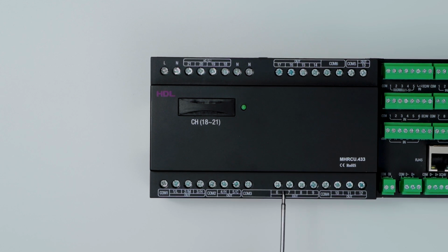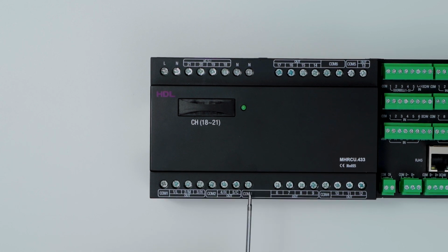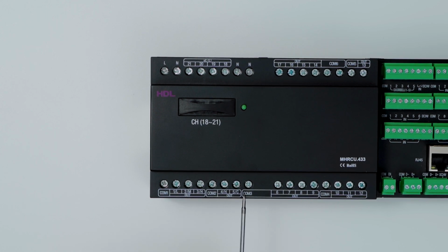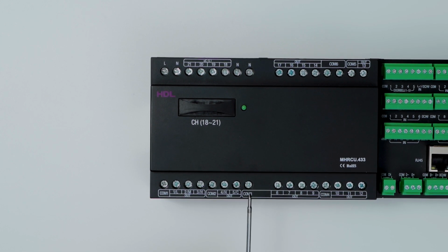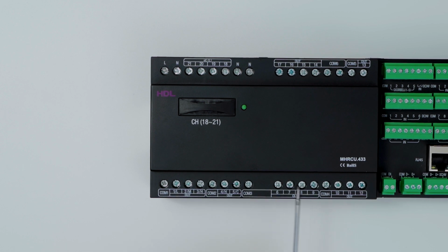Similarly, COM6 can be used for similar purposes. It's essential to note that if you're using a high-voltage motor, you can connect it with the live wire of other COM ports. However, if it's a dry contact motor, it needs a separate power supply to avoid damaging the equipment. COM4 is suitable for connecting switches controlling light fixtures. Like the other COM ports, COM4 also requires power supply.